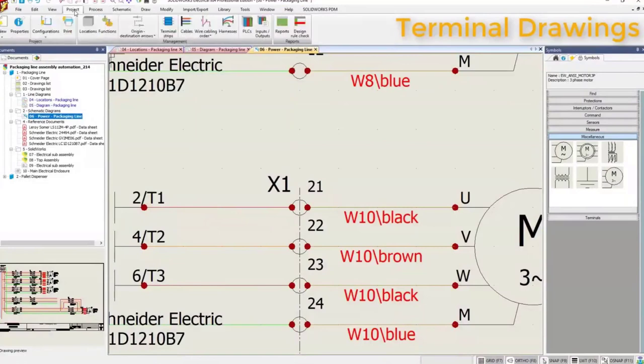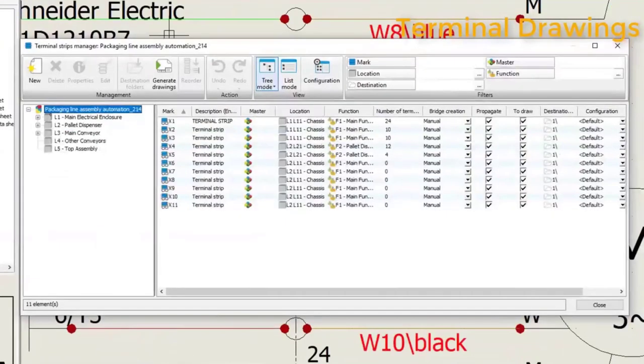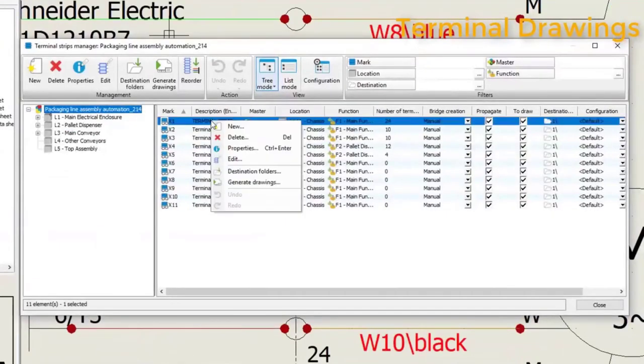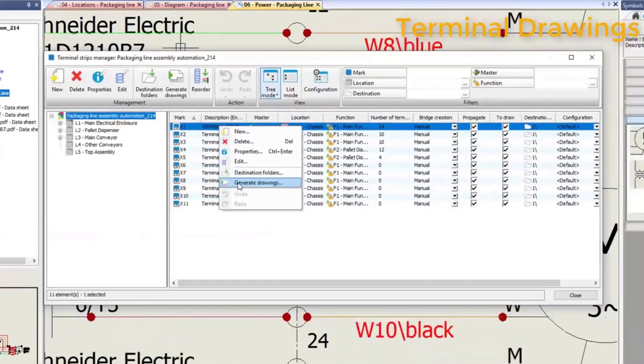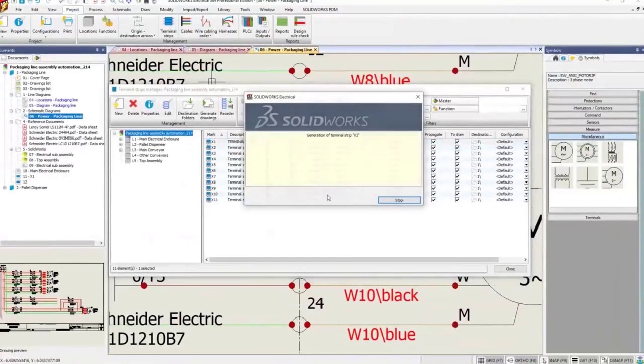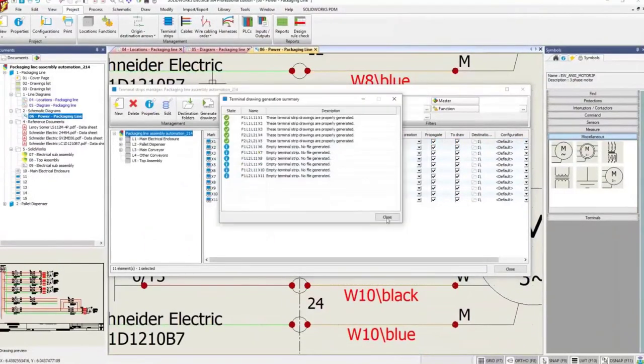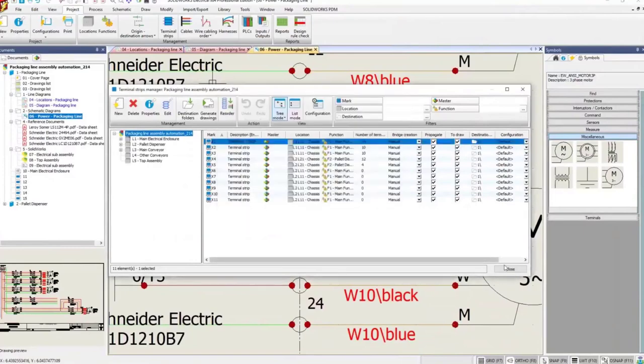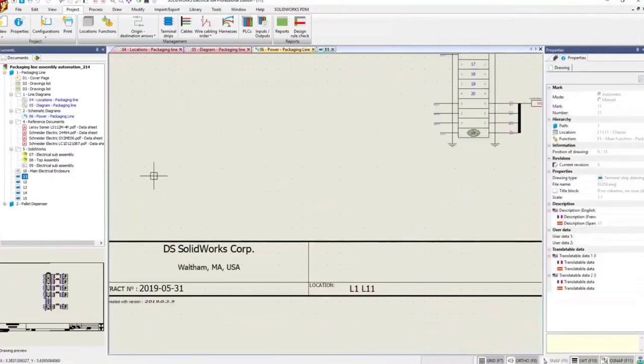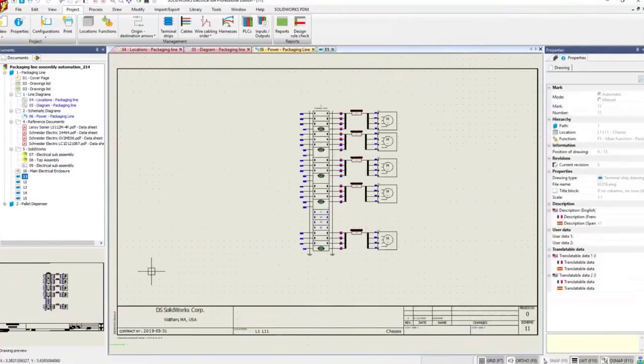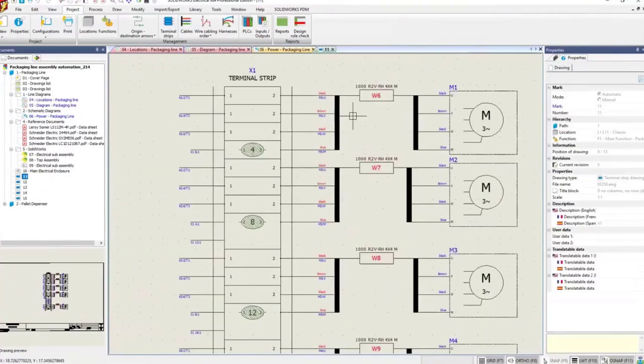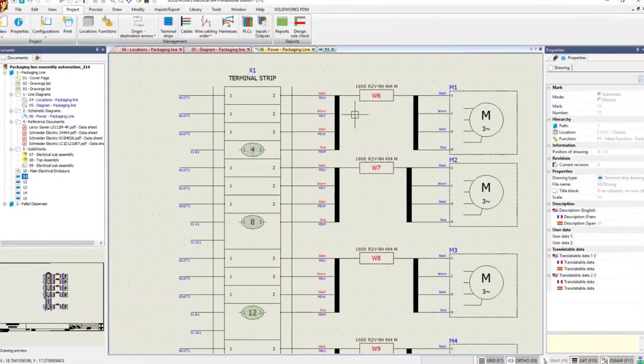Once we set up our terminal strip drawings, we can generate all those drawings from our schematics. So I'm going to go ahead and generate all the terminal strip drawings for this project. I have terminals all over every single sheet. Maybe they have bridging, maybe they have cables and so on. All that can be drawn for me according to the configuration that I've set up. That's what you see here. So no longer does manufacturing need to go and write out every terminal what it's connected to and then go at it or no longer do you have to create an independent drawing of this information. You can parametrically generate that information.